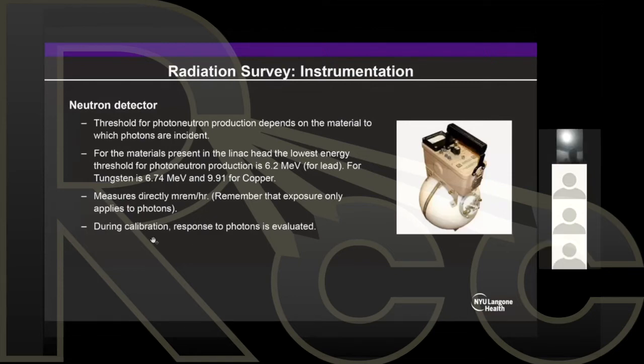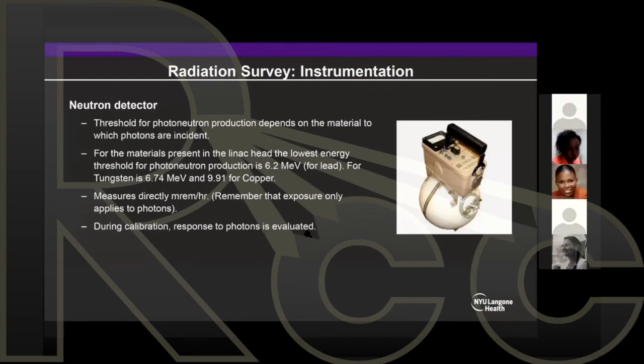And during calibration, the response to photons is evaluated just to make sure that it's not over-responding to photons and you get a measurement that is higher than expected. And this is actually a pretty heavy detector. It doesn't look like that. When I was doing a radiation survey with some of my fellow residents like a year and a half ago, we were like, okay, now it's your time to get the neutron detector, because here you have this cadmium lined moderator, and then inside you have your detector. So it's actually heavier than it looks.